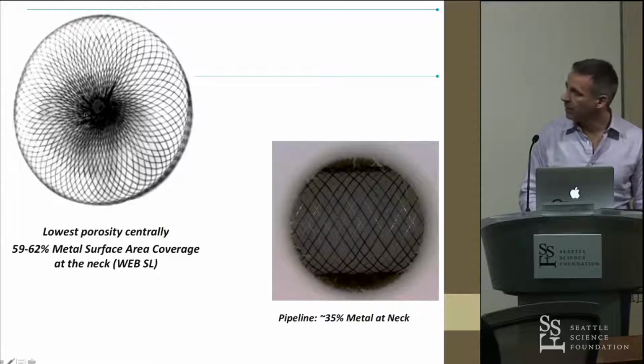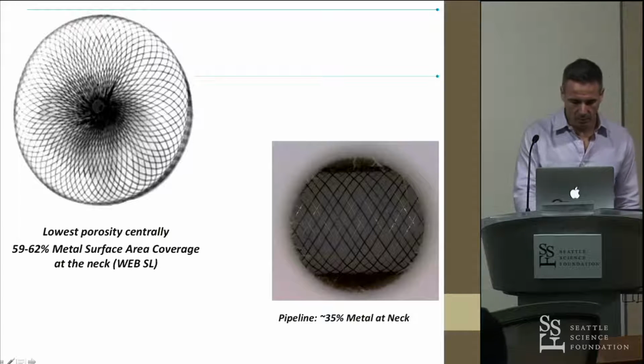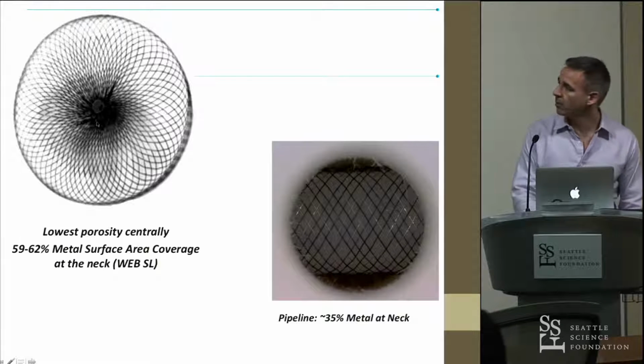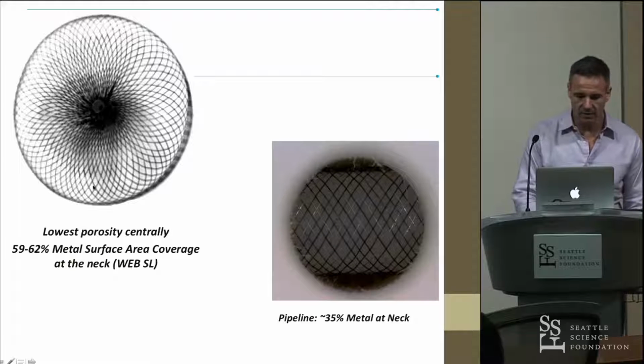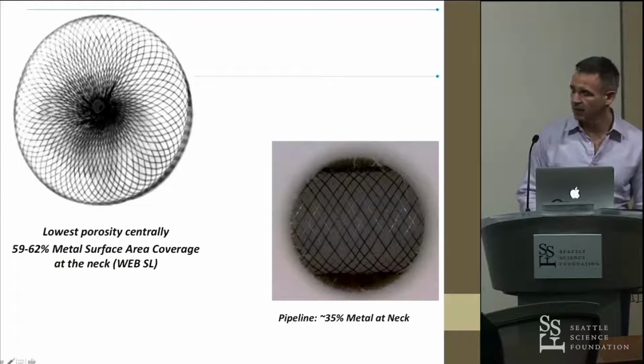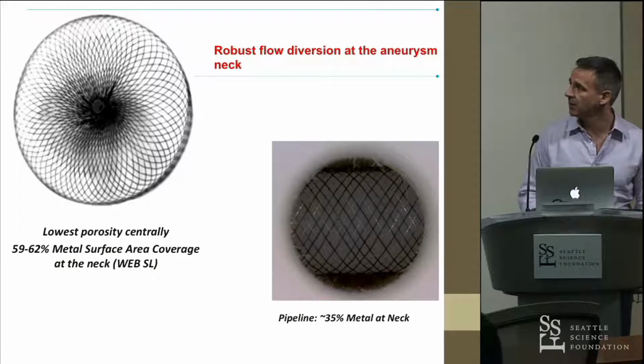And so if we look at the WEB device at the interface between the parent vessel aneurysm complex, these microbraids actually have a very, very low porosity and a very low pore density. And so the porosity centrally is 100% where all the microbraids converge on the marker. But as we go out distally, that decreases. But the smallest level of metal surface area coverage that you get anywhere in the WEB is about 60%. And that's versus a Pipeline that has about 35% metal surface area coverage at the neck. And so a WEB is like 2 perfectly placed Pipelines where there's no overlap of the strands. And so you can imagine the level of flow diversion that this gives you at the neck of the aneurysm.